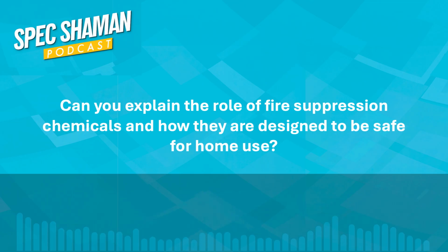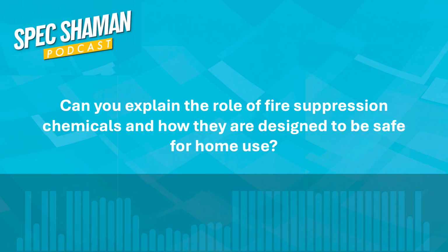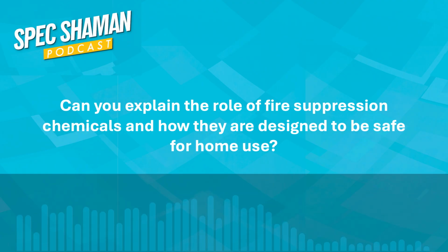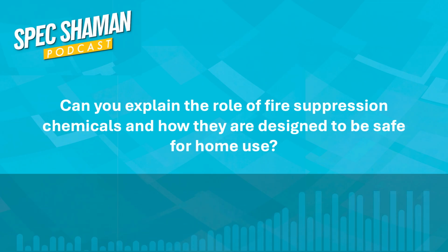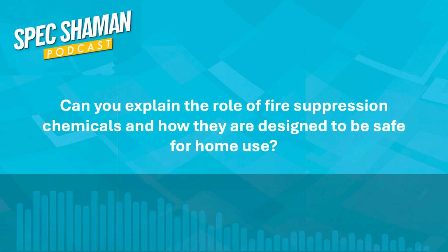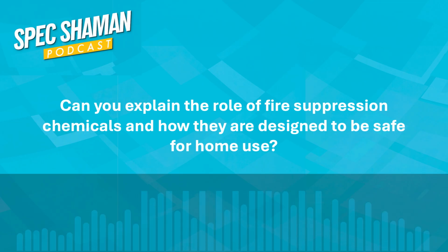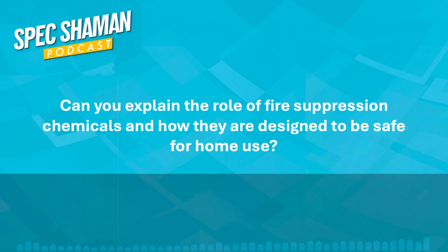One requirement of UL 300A is that the fire has to stay out for 5 minutes. So it not only puts out the fire and reduces it below the flash point needed to auto-reignite, it also puts a surfactant on the cooking oil or other substrate, which robs it of oxygen. So it does two things: it's below the flash point and it can't get oxygen to burn. It does this very effectively. I've seen tests where the burner was left on, and it will not even reflash for 40 minutes, because it can't get oxygen into the substrate, which is the fuel for the fire.